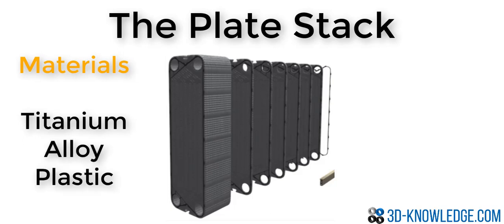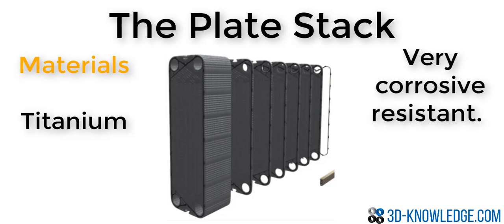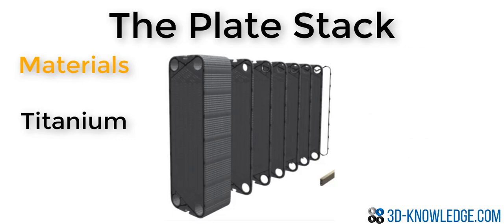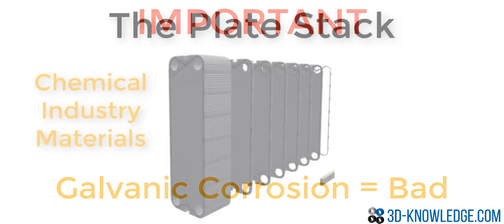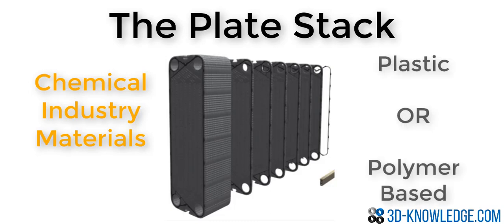The plates themselves can be manufactured from a number of different materials, ranging from titanium to different alloys, as well as plastics. Titanium is chosen whenever the environment is particularly corrosive, as it has excellent corrosion resistance — but it's incredibly expensive. Another disadvantage with titanium is that any metal connected to it will act as an anode due to galvanic action; when two dissimilar metals are connected, one is the anode and one the cathode, and the anode slowly wears away. Protection can be achieved by insulating the plate from the dissimilar metal or by installing a cathodic protection system. For some chemical processes, the plate will be constructed of plastic or a polymer-based material.